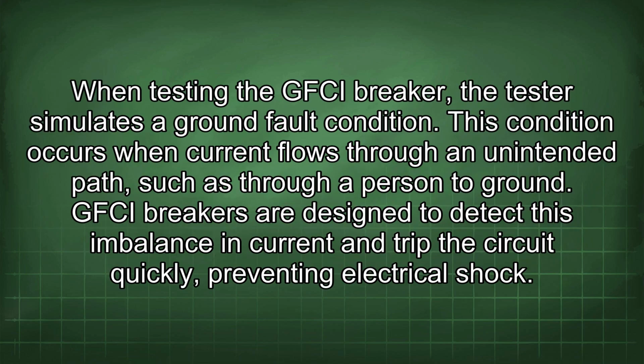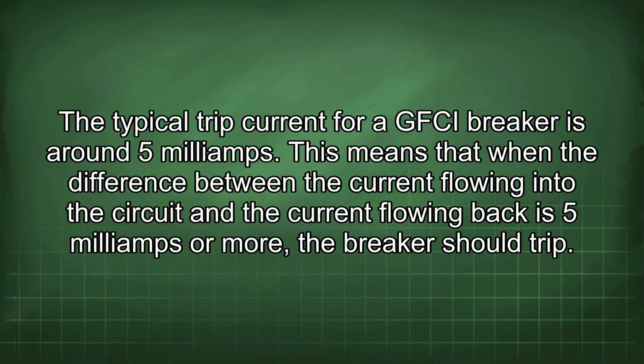When testing the GFCI breaker, the tester simulates a ground fault condition. This condition occurs when current flows through an unintended path, such as through a person to ground. GFCI breakers are designed to detect this imbalance in current and trip the circuit quickly, preventing an electrical shock. The typical trip current for a GFCI breaker is around 5 mA. This means that when the difference between the current flowing into the circuit and the current flowing back is 5 mA or more, the breaker should trip.